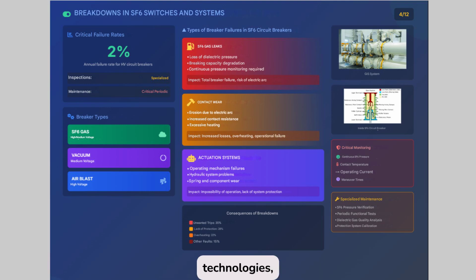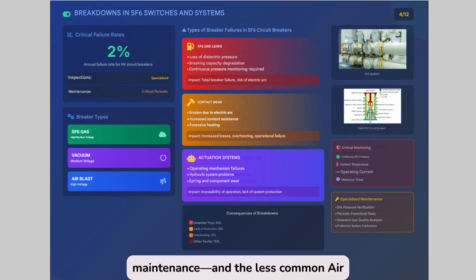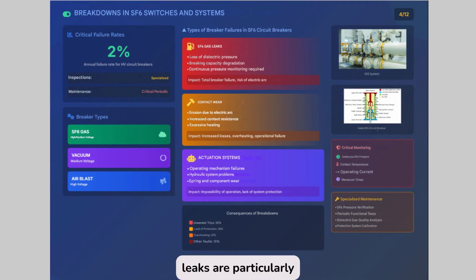Among the most common technologies, SF6 gas circuit breakers stand out due to their insulation efficiency, followed by vacuum circuit breakers, which require less maintenance, and the less common air blast circuit breakers. Among the most significant faults, SF6 leaks are particularly worrisome. Reducing gas pressure compromises insulation and increases the risk of arc flash. Furthermore, SF6 is a greenhouse gas, which also introduces an environmental and regulatory dimension. Another common fault is contact wear, the result of repeated operations that generate overheating and increased electrical resistance. Added to this are failures in actuation systems, which can prevent the breaker from opening or closing, leaving the system unprotected in the event of a fault.